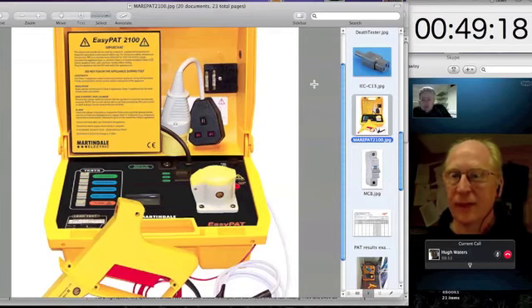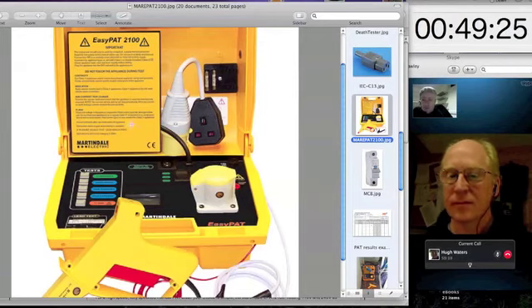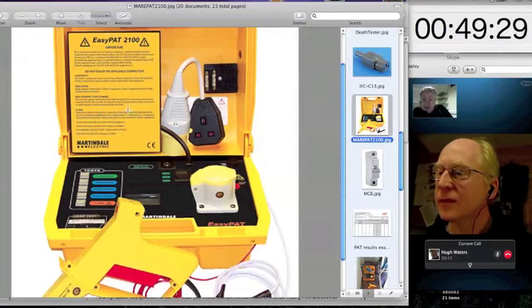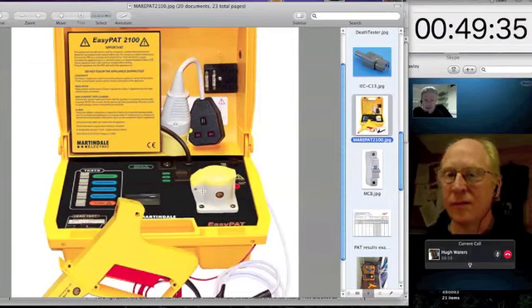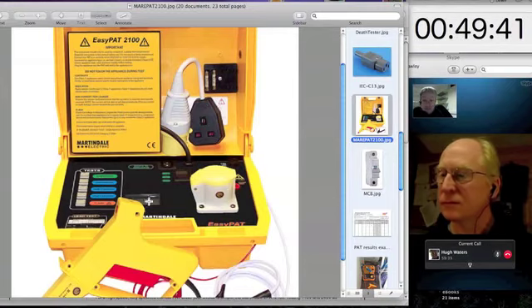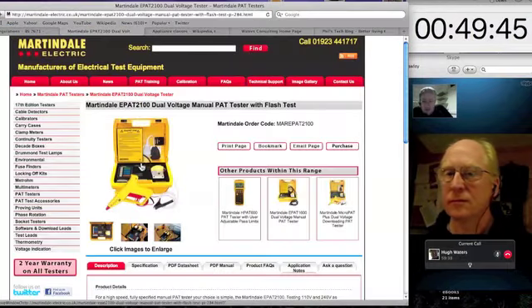So you can see, just looking at our PAT tester here, it comes with the cord here, which is actually wrapped up inside the instruction plate. There is just a regular 13 amp mains inlet cord, and there's a 13 amp outlet, and there are various inlets. There's an IEC inlet there, and there's also an outlet for 110 volt stuff as well, because it can test both standards. And then we've got 5 buttons down the side here and a little display. In fact, let me pop up the web page for Martindale, and that may give us a bit more of it. No, it's exactly the same picture, isn't it?